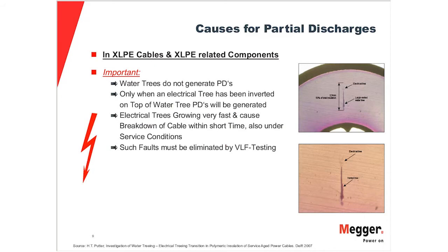Okay, as I have already explained with my previous comments, water tree does not generate PD only if they convert into electrical trees. If you do VLF testing on your cable, VLF which is seen as a pressure test on your cable, you would make these water trees to nicely grow during tests. And the aim of a VLF or pressure test is to break down the critical water tree during test, so that they do not break down afterwards.